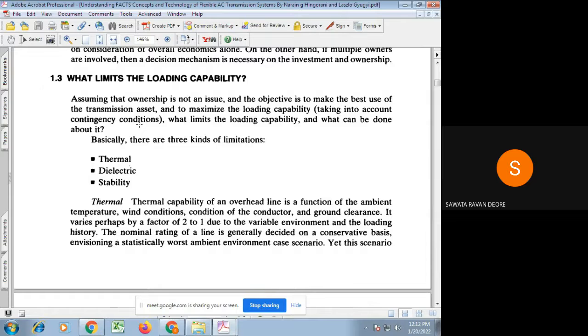So all these factors are going to decide at what actual current that transmission line can be operated. And based on that, the actual power or thermal rating of that line is decided. Out of these physical parameters, some parameters vary. Let's say ambient temperature varies seasonally. In winter, it is low. In summer, it is high. So according to that, the current handling capacity of that conductor is also varying seasonally.